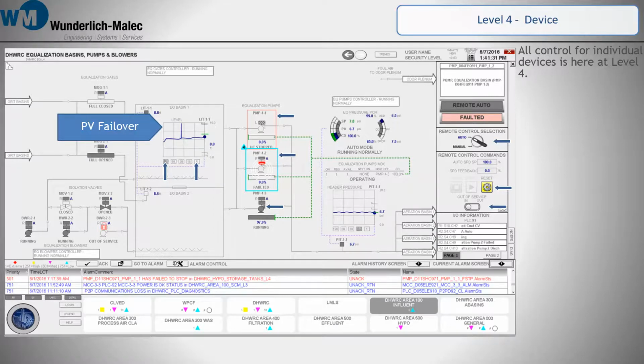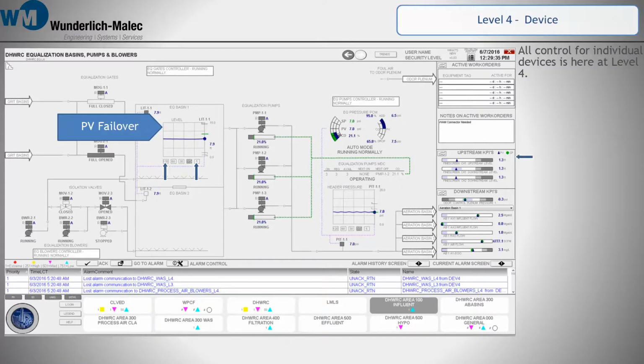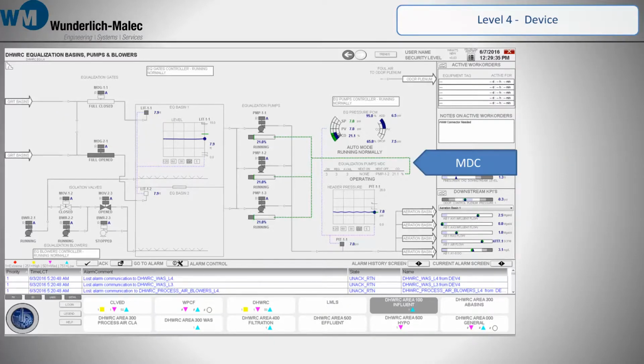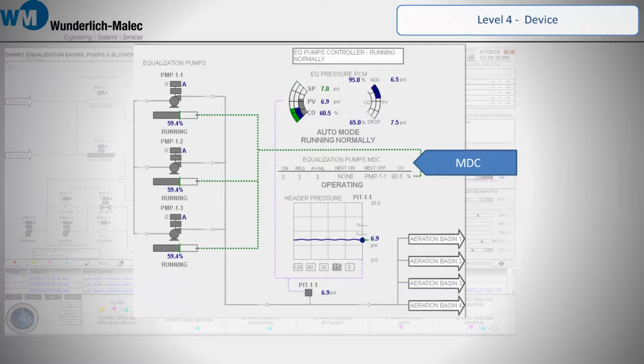And being at the lowest level, we have the narrowest view of how the plant is operating. So now we have upstream and downstream KPIs, so the operator can continue to keep an eye on the area's health. The MDC, multiple device controller, handles lead lag, first on first off, or duty cycle, giving the operator all the information required. The purpose of the PCM is to provide analog PID control for level, pressure, flow, or temperature to either a single device or to be used in tandem with an MDC for control over multiple devices.